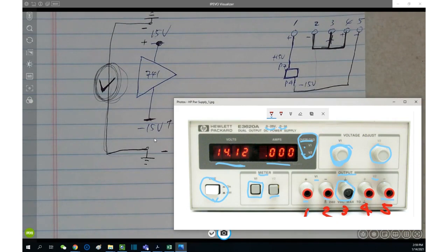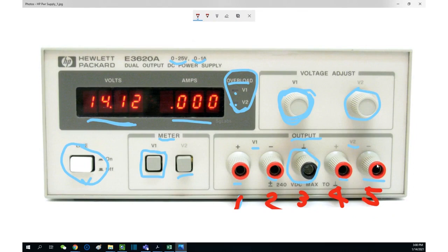In the case of like two and four, aren't they like automatically grounded for some power supplies? Right, as always see, this odd number of terminals, how do you understand this? This first a pair of positive and negative is one differential output. The ground is floating, waiting for you to determine. So the negative is not representing the ground, it's floating. Same thing to this pair of positive negative. So in this particular case, you are having a positive negative 15 output, you are having a positive negative also 15.